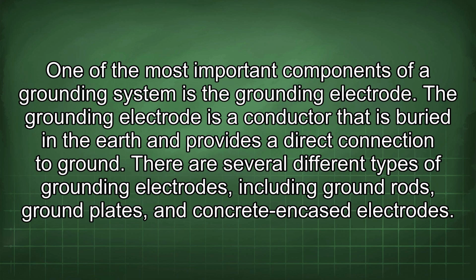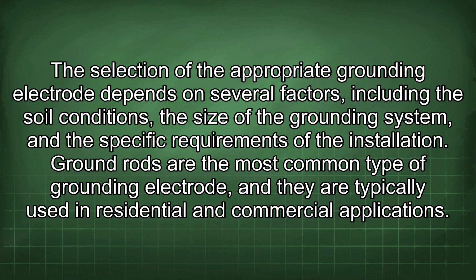One of the most important components of a grounding system is the grounding electrode. The grounding electrode is a conductor that is buried in the earth and provides a direct connection to ground. There are several different types of grounding electrodes, including ground rods, ground plates, and concrete encased electrodes. The selection of the appropriate grounding electrode depends on several factors, including the soil conditions, the size of the grounding system, and the specific requirements of the installation.